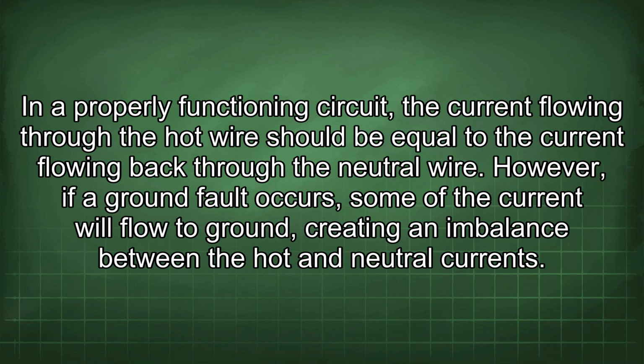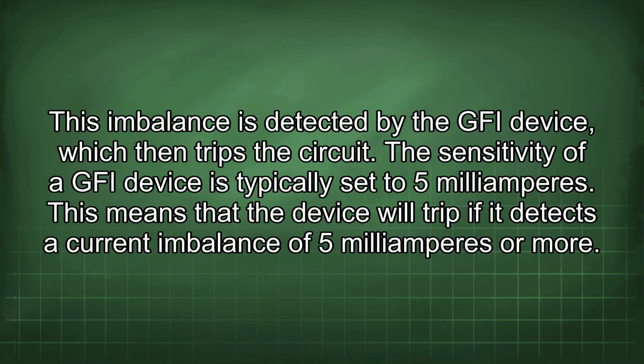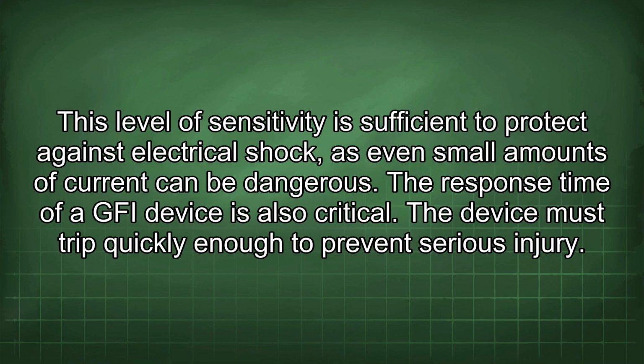In a properly functioning circuit, the current flowing through the hot wire should be equal to the current flowing back through the neutral wire. However, if a ground fault occurs, some of the current will flow to ground, creating an imbalance between the hot and neutral currents. This imbalance is detected by the GFI device, which then trips the circuit. The sensitivity of a GFI device is typically set to 5 mA. This means that the device will trip if it detects a current imbalance of 5 mA or more. This level of sensitivity is sufficient to protect against electrical shock, as even small amounts of current can be dangerous.